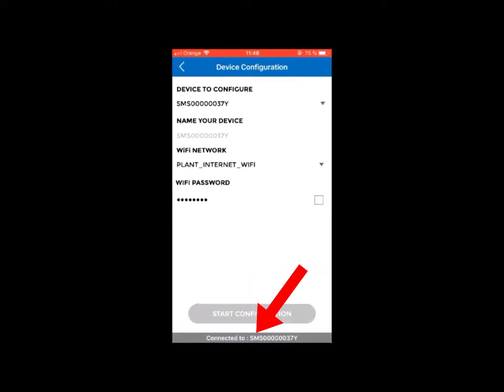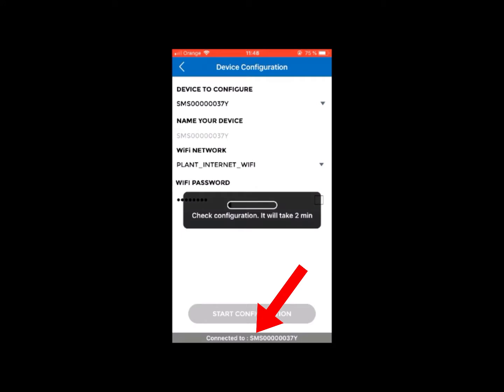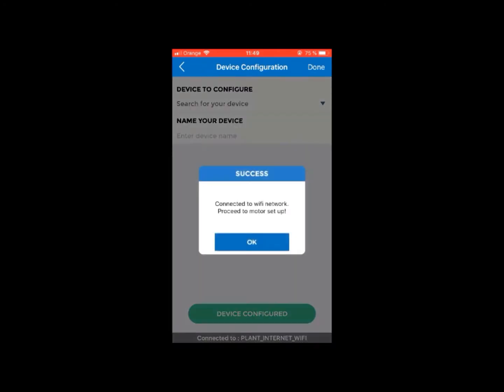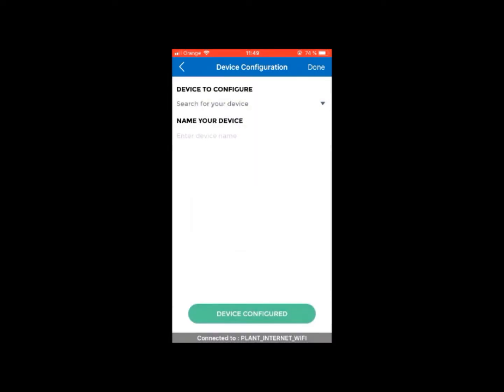Once these fields are completed, click on Start Configuration at the bottom of the screen. For approximately two minutes, the application will run checks between the smart motor sensor network and the plant network. If the connection between the device and the Wi-Fi network is correct, a confirmation message will be displayed. Click OK in the message and then click on Done.